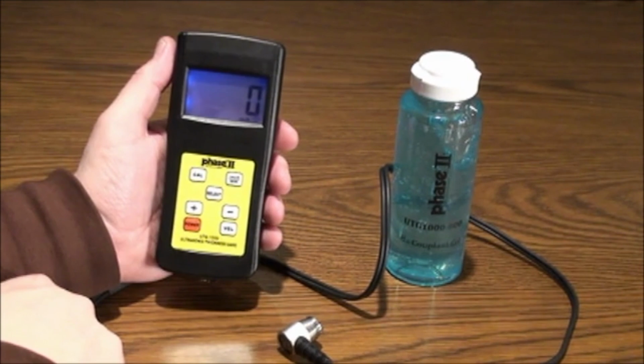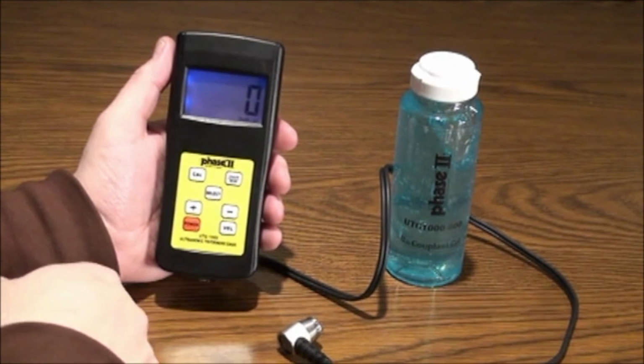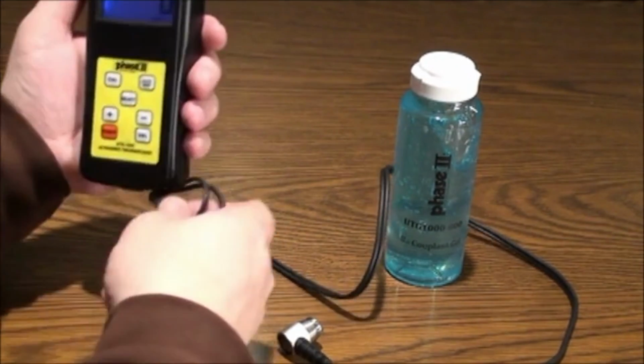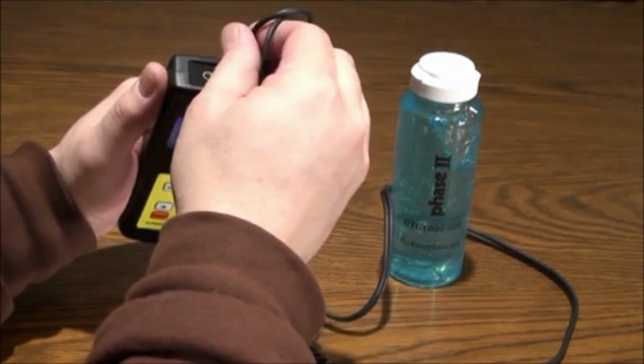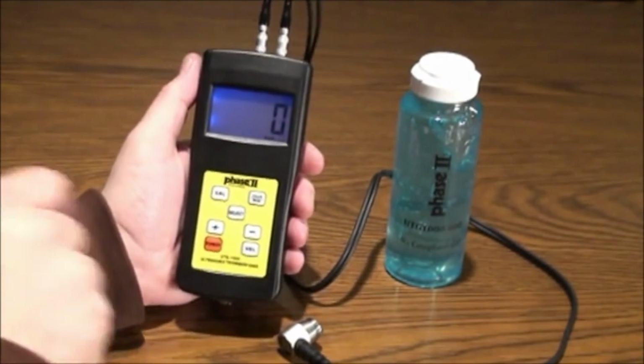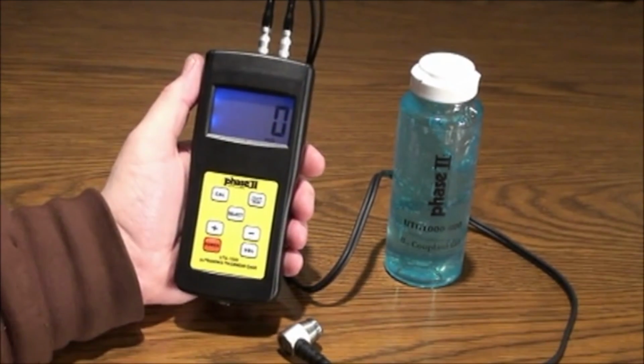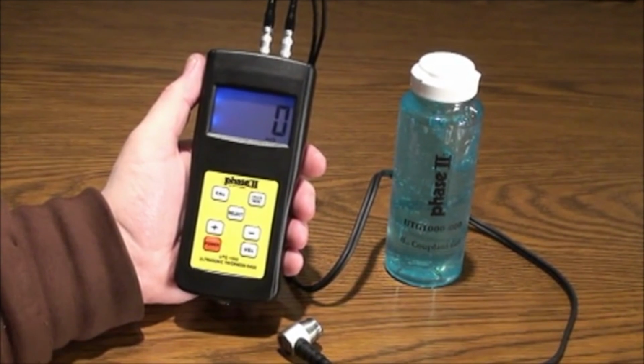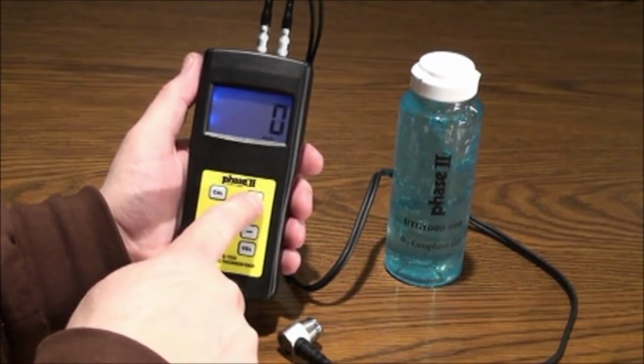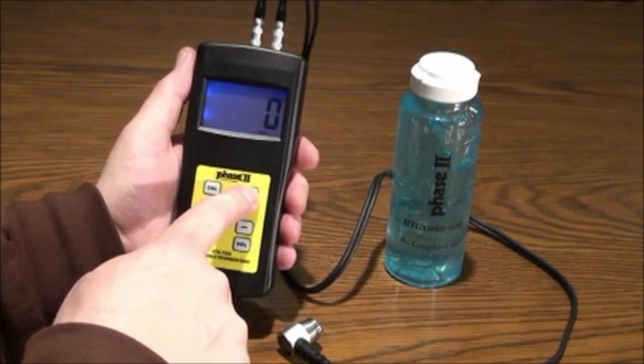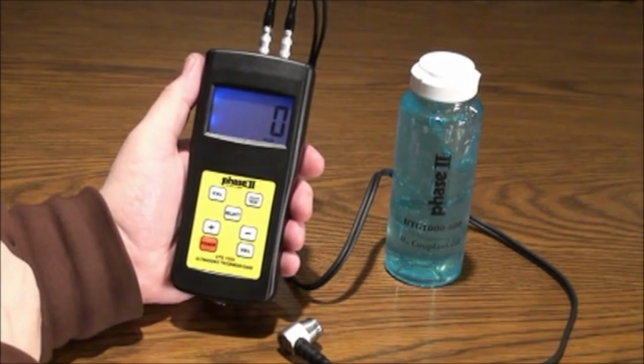To begin, insert the plugs of the transducer into either of the plugs in the gauge. Press the power button to bring up the interface. The inch metric button on the top right will allow you to toggle between inch-metric readings. This will also determine the velocity setting reading in inch-metric as well.